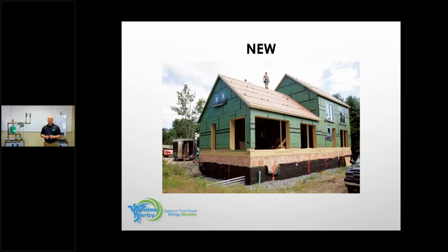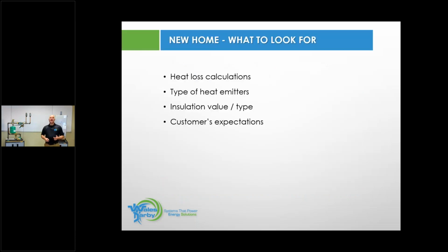That's going to be a conversation had with the person asking you to replace this piece of equipment. So here we have Bob the builder up on the roof. We have the conversation with him, and it looks like this. Does he have the heat load calculation? Yes or no? If he does, great. If not, somebody's going to have to do that, whether it's you, the engineer, or whoever is on that home. Someone has to do that heat load, or we are lost at that point. It's always good to understand the type of heat emitters they want in that home. Is this going to be a hydro air system?